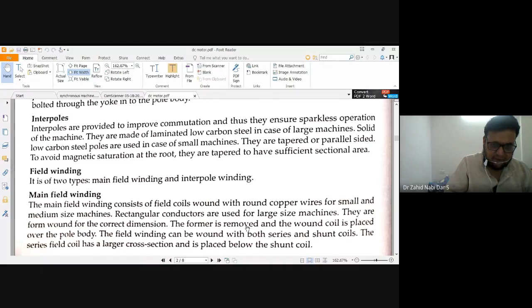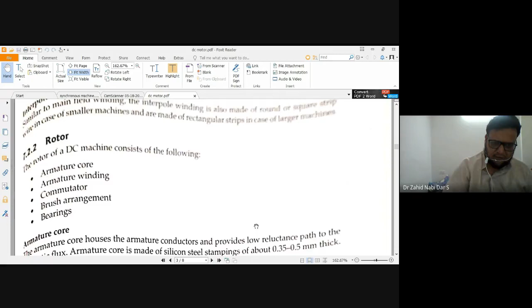Field windings, you can see, are of two types: main field and interpole winding. The main field winding consists of round copper wire for small and medium sized machines and rectangular conductors for large machines. Now let's go to the rotor side. The rotor has the armature core, winding, commutator, brush arrangement, and bearings. The commutator brush arrangement is on the rotor only, not on the stator side. The interpole and compensating winding are on the stator side, whereas these other arrangements are on the rotor side.